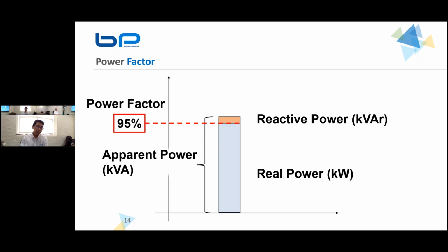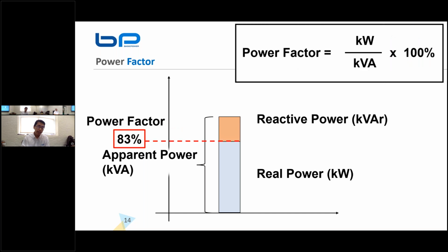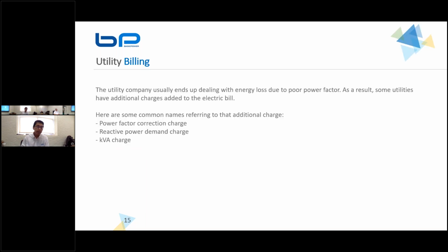Power factor really is just the ratio. It's the ratio between the actual beer you have out of the total amount that you paid for. In this case, as your ratio changes, your power factor changes. So this is a simple formula you can use when you look at your utility billing to calculate what your power factor might be. Sometimes your utility actually reports your power factor, so you can calculate your kVA or vice versa. The reason for this is because utility billing, they usually add additional charges when it comes to having poor power factor in your utility spendings.